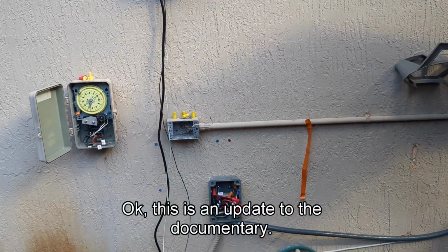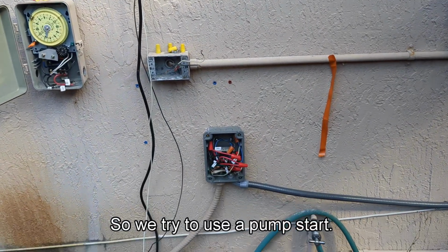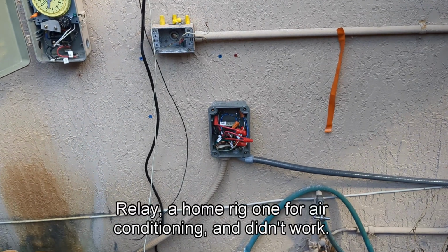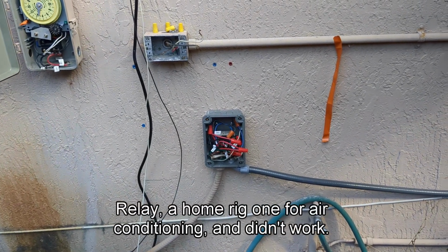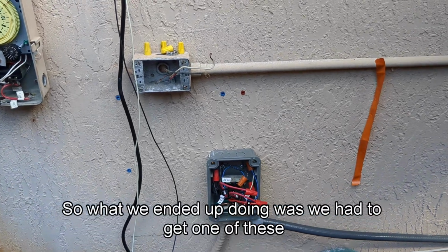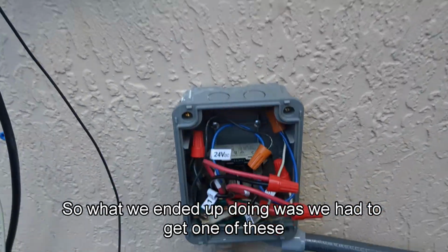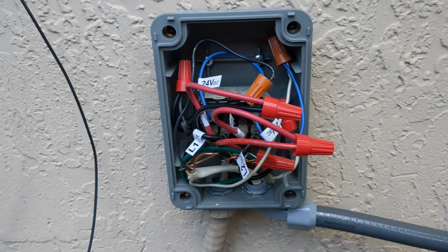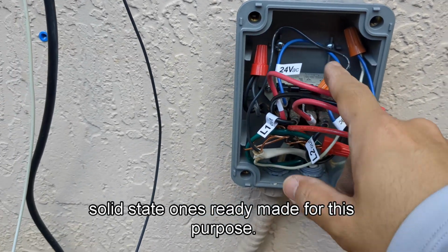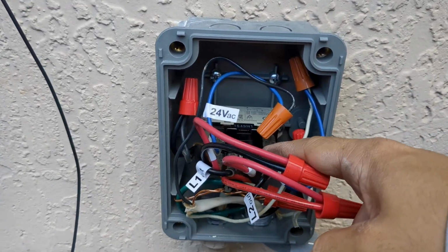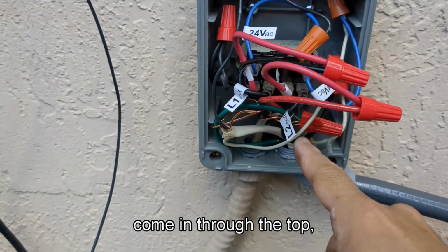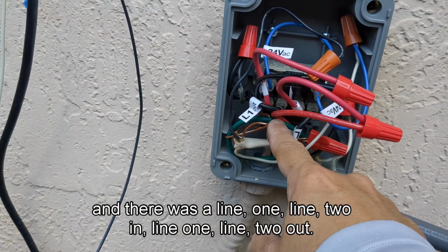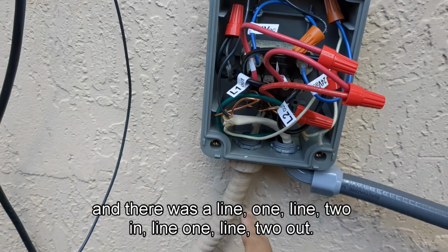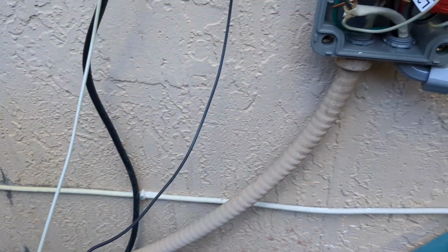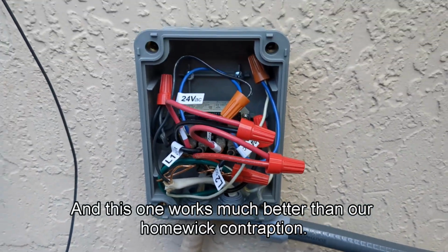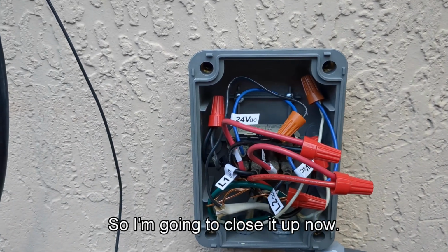Okay, this is an update to the documentary. So we tried to use a pump start relay, a home rig one for air conditioning, and it didn't work. So what we ended up doing was we had to get one of these solid state ones ready made for this purpose. So the 24 volts come in through the top, and there's a line 1, line 2 in, line 1, line 2 out, and that's where it runs out to the pump. And this one works much better than our home rig contraption. So I'm going to close it up now.